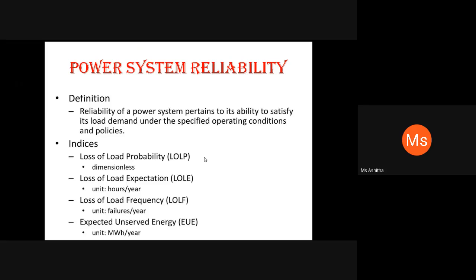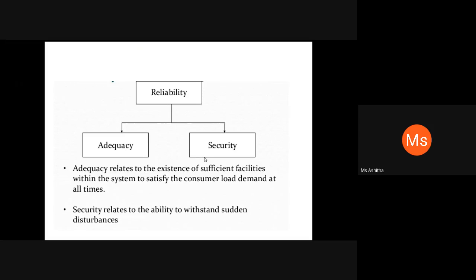Next comes power system reliability. The reliability of a power system pertains to its ability to satisfy its load demand under the specified operating conditions and policies. The different indices of power system reliability are loss of load probability, loss of load expectation, loss of load frequency, and expected unserved energy. Reliability mainly consists of two parts, adequacy and security. Adequacy relates to the existence of sufficient facilities within the system to satisfy the consumer load demand at all times. Security relates to the ability to withstand sudden disturbances.